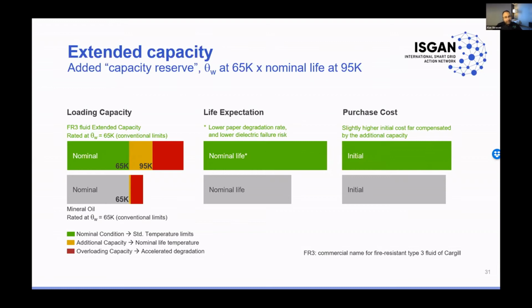Then when we talk about the purchase cost, when we have the same size, designed to the same temperature limits, we would expect a little bit higher initial cost, right? But this would be by far compensated by the increased loading capacity. If you go in the other direction, as Angelo presented in the greenfield, we would have a more compact transformer with lower usage of materials and potentially even cheaper.